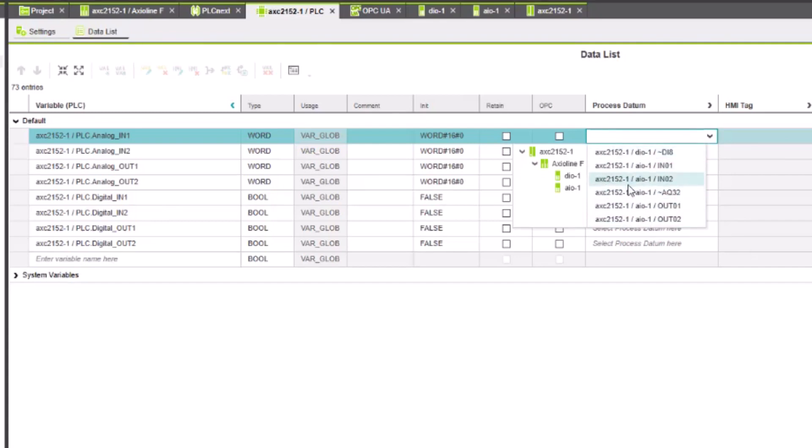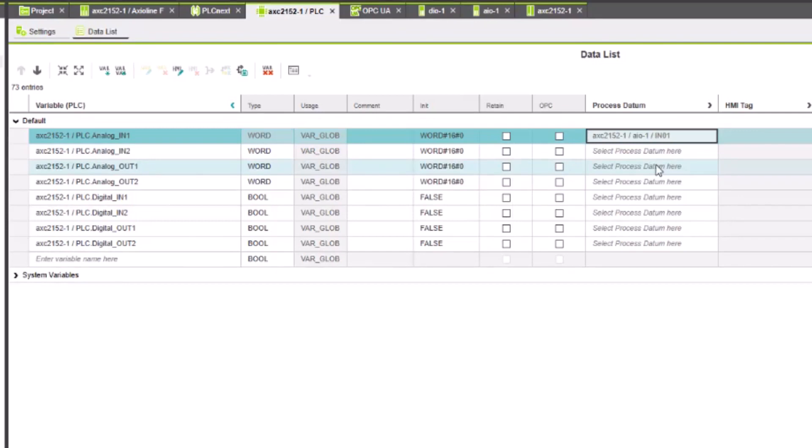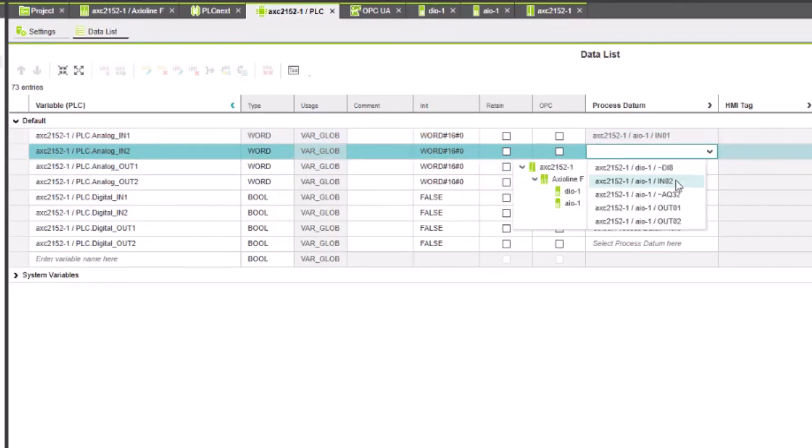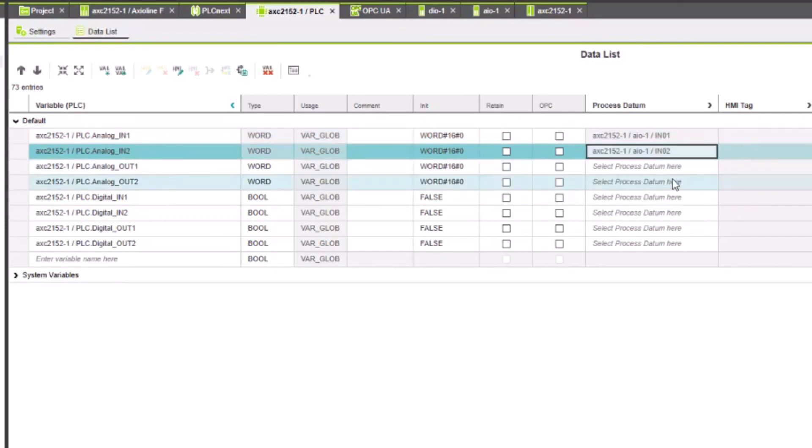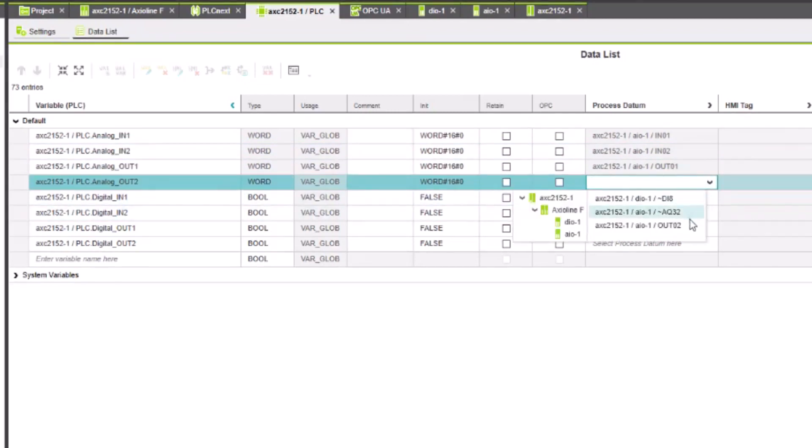So this is a word and it's an analog input. It already knows that it's a word in this selection. So it's not giving me the bit-based digital inputs or outputs. This DIO 1 through 8 is actually all of the IO lines in a group. So it is a special read for the digital lines. Analog lines also have a word, effectively a double word 32-bit mode, which is this one here, which can bring two, I think, two analog ports at a time as well. So what we actually want is the IN1, which is this one here. And then the next one would be IN2. And we've got the outs for the analog now. So ANALOGOUT1, ANALOGOUT2.